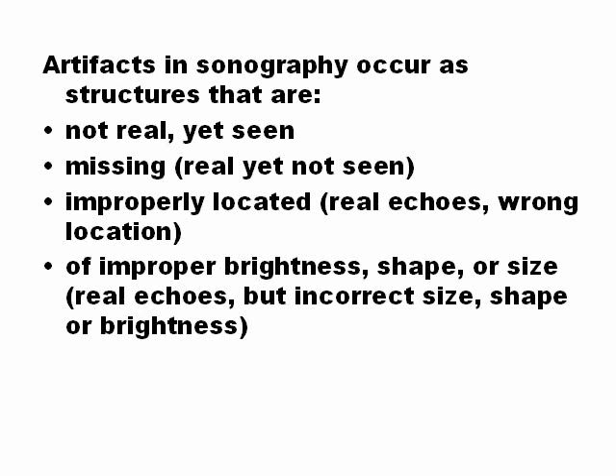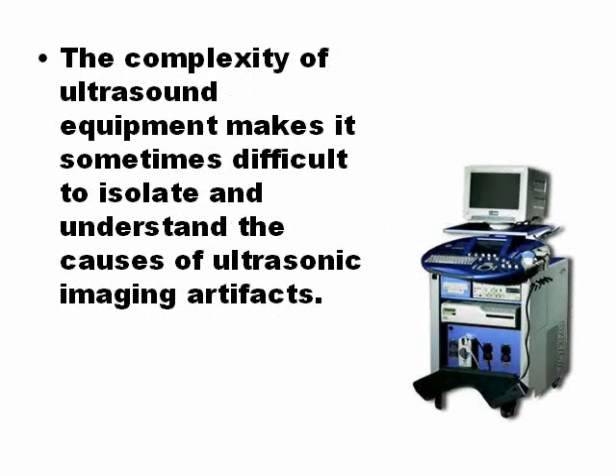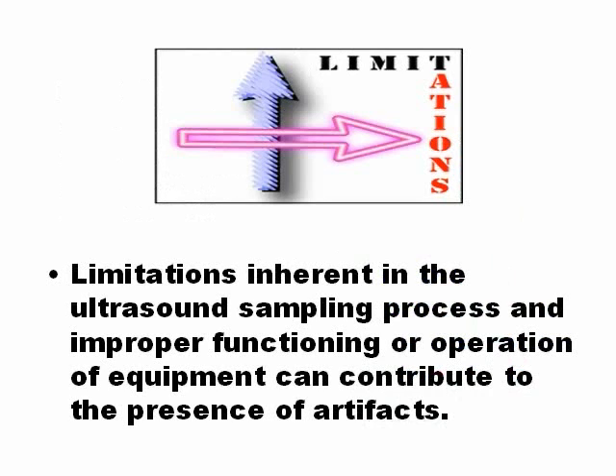Artifacts are not real, but sometimes the complexity of the machine and the ultrasound don't let you know exactly what the reason for the artifact is. Sometimes it is the mix of two different causes. Limitations of ultrasound, the sampling process, and improper work of the machine are sometimes the cause of ultrasound artifacts.